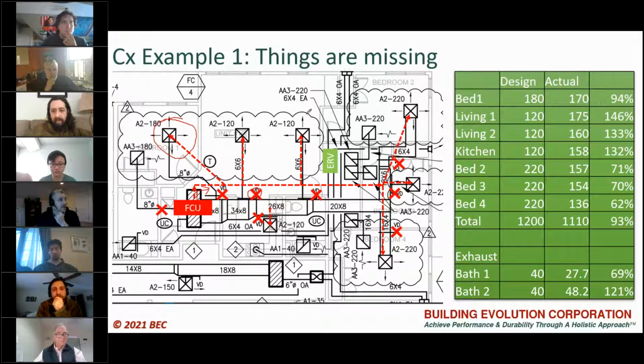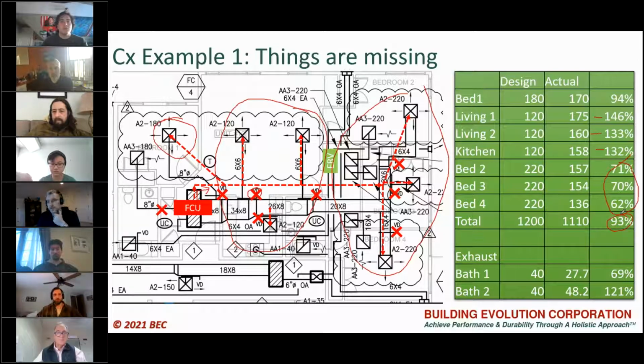That's not too bad. But if you look at the open plan space here, 46% over, 33% over, and 32% over on CFM. That open plan space is sucking up all the air, basically. And if you look at these 3 bedrooms at the end of the line, they're under capacity. But overall, it's within 7% of the total system. So if you're just looking at the overall airflow, it looks good. But it's not getting to where it should be.